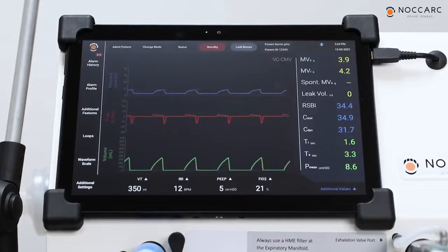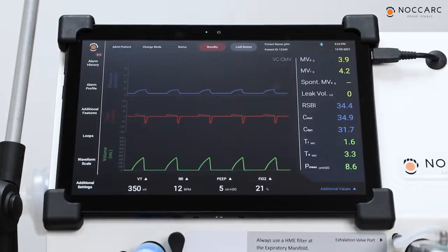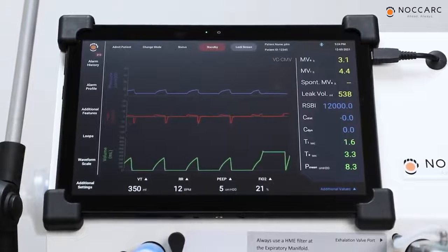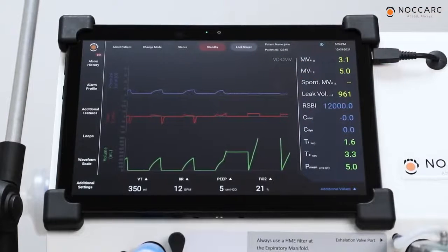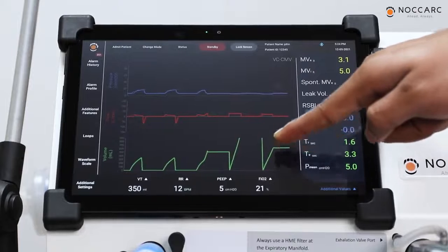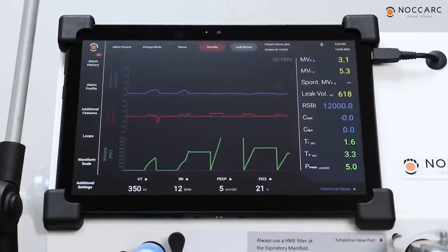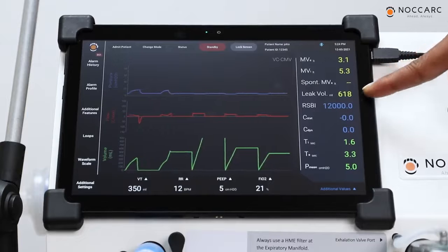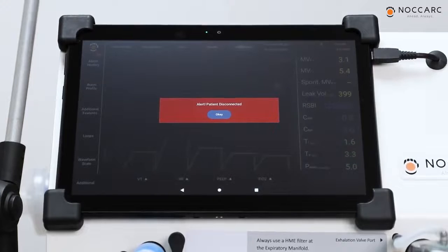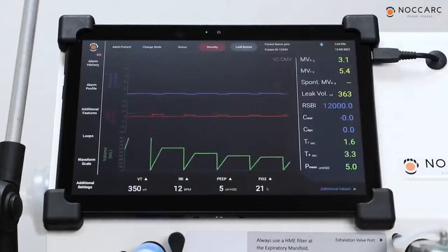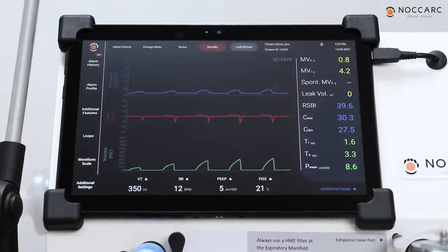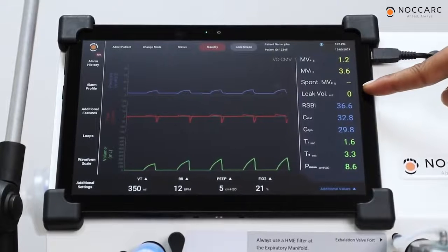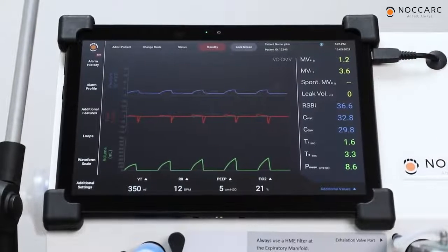To simulate leakage condition, I will remove the knob given on the active exhalation valve. Now patient tube from inspiratory to expiratory is having leakage. On the graph you can see leakage is displayed. Similarly, in the leakage volume parameter, what amount of leakage is there will be displayed. At the same time, patient disconnected alarm will come on the screen. Press on OK. When leakage is restored, in the leak volume parameter, it will again show 0.